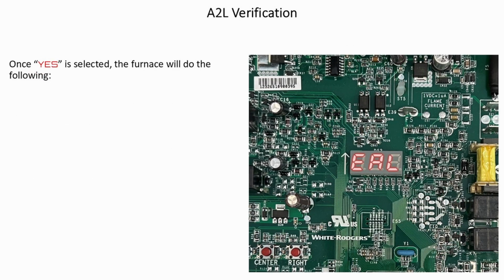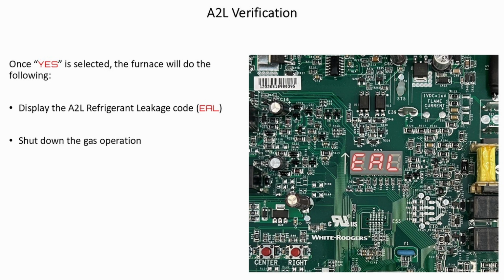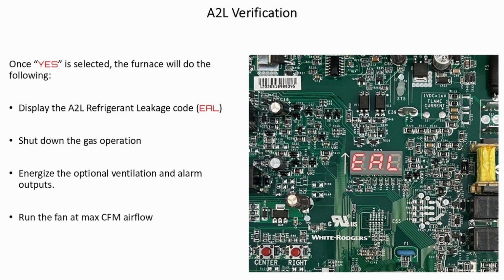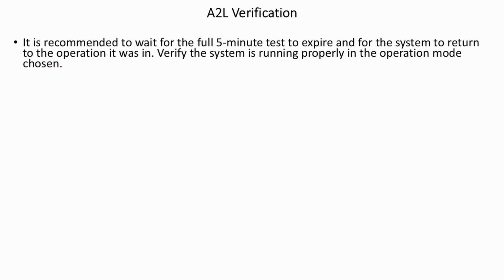Once Yes is selected, the furnace will do the following: display the A2L refrigerant leak code, EAL. Shut down the gas operation. Energize the optional ventilation and alarm outputs. Run the fan at maximum CFM airflow. It is recommended to wait for the full 5-minute test to expire and for the system to return to the operation mode it was in. Verify the system is running properly in the operation mode chosen.